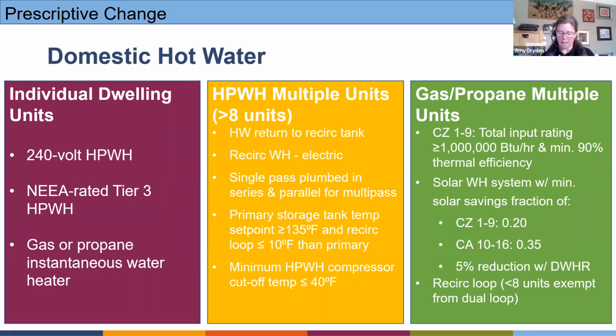And what the prescriptive thresholds are for it. So what we have here are some requirements for return temperature and operating temperature, where we're optimizing because we want to see some differential between what we're supplying and the return temperature coming back. We want the hot water return to go to a tank and not to the primary heater itself. If we have a recirc water heater, because some systems will have a dedicated recirc water heater, so you may have a large central plant, and then your recirc is being maintained by an individual water heater, that needs to be electric. It can be electric resistance or heat pump, but it needs to be electric.